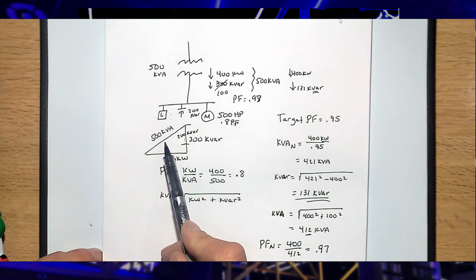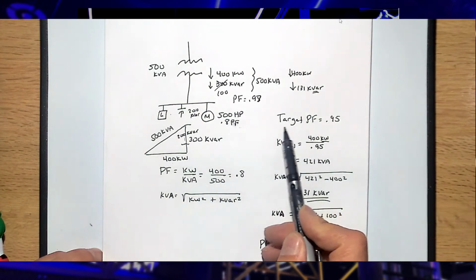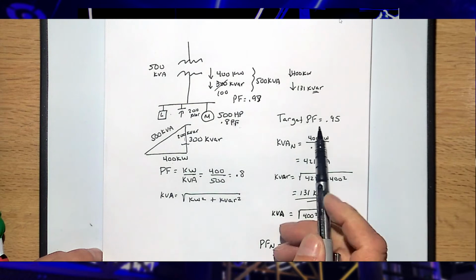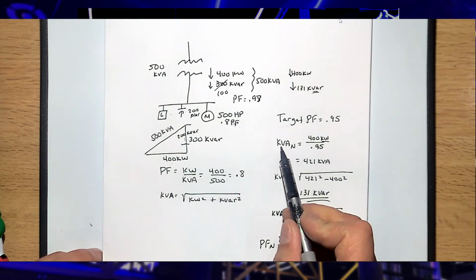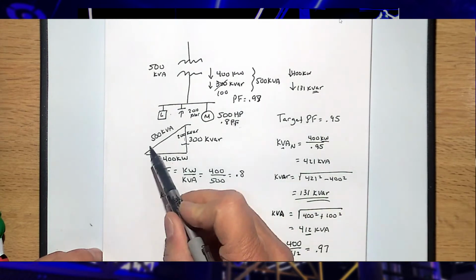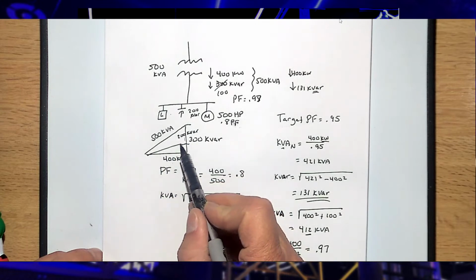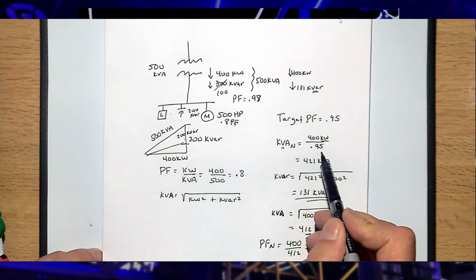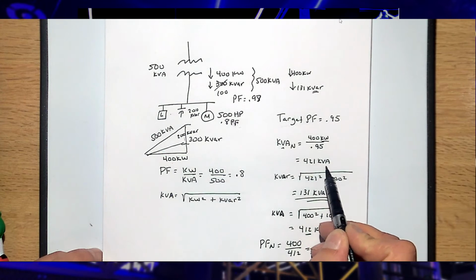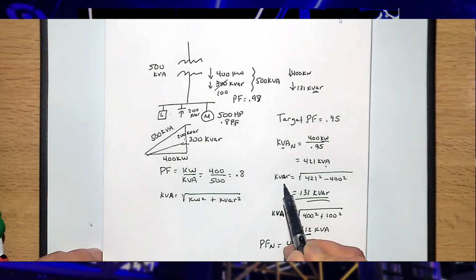Right. So let's say you wanted to put a capacitor in, and your target power factor was 0.95. My new kVA would be 400 over 0.95, or 421 kVA. So I can calculate my kVAR: 421 squared minus 400 squared. It's just a right triangle. So I get 131 kVAR.